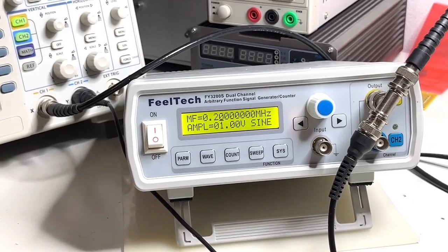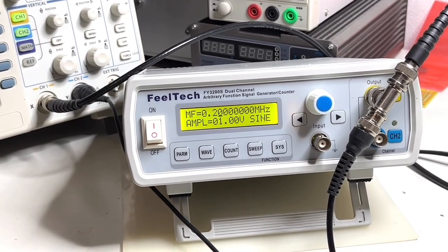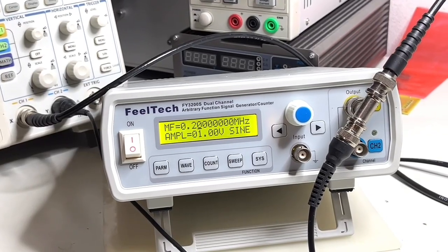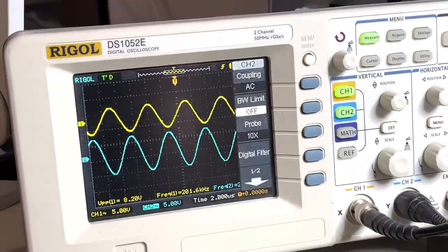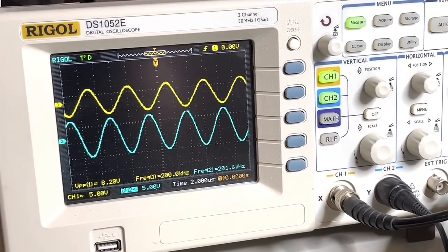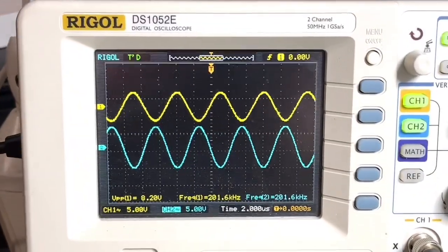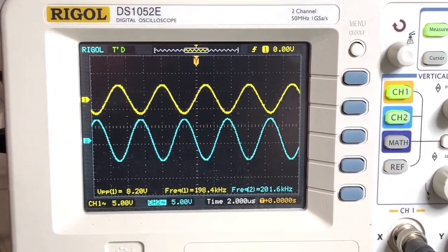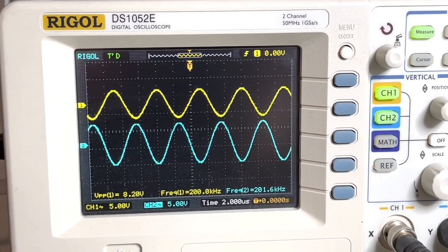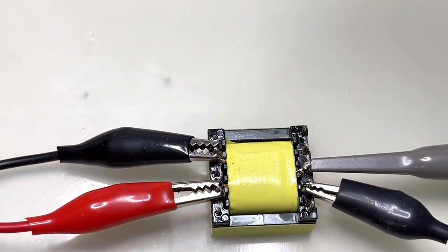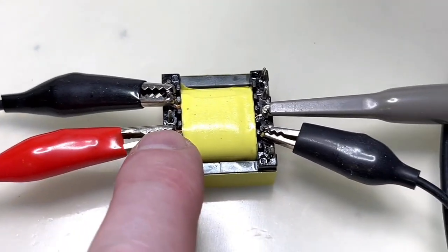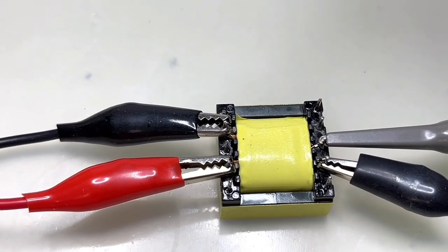So the last item I want to show you is how to determine the phase between the primary and the secondaries of one transformer. Now I have a transformer and I want to find out the phase relation between the windings — is it in phase or out of phase? Here the way I've connected it: the primary — yellow trace — is 180 degrees out of phase with the secondary — blue trace. This is how I connected it.